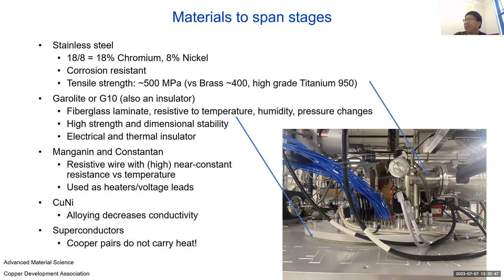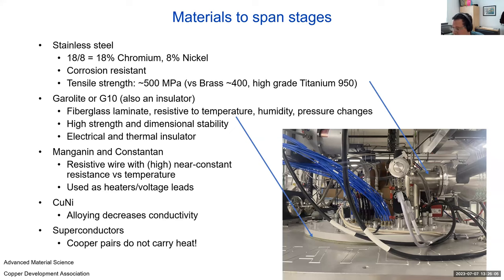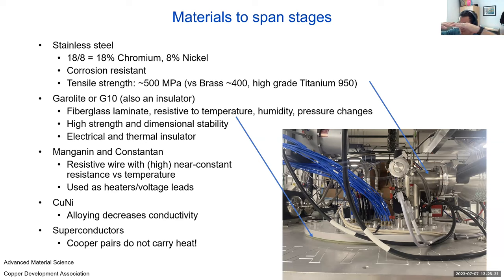A quick question: do you anneal OFHC copper after machining and does it matter? In principle it would be good to anneal it in a vacuum oven. However, annealing often makes it so soft that it won't hold its shape anymore. In some machines we take OFHC and weld it, which has the property of accidentally annealing it — you can bend them with your hands. In general, if it is a bendy, flexy thing, sure, anneal it. If it is something like a fridge plate that should hold a shape, no.